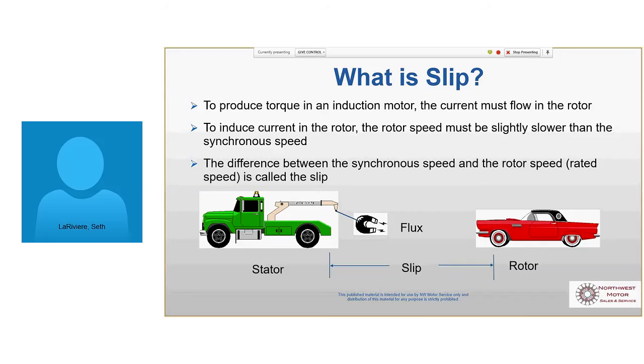So that's kind of what this is showing us here. The difference is called slip, and you can refer to that motor any way you want. You can call it a 3450 or a 3600. I'll know what you're talking about. Anybody would. And then the voltage, that's always on there. Frequency, that's always on there, usually going to be 60 though. And then the amps, that's always going to be on there. So those first 5 things, all manufacturers are going to give you. After that, there's a lot of stuff that not everybody puts on there.